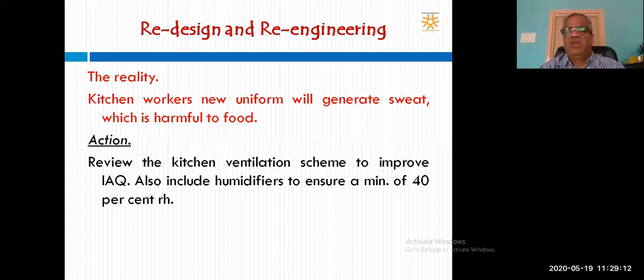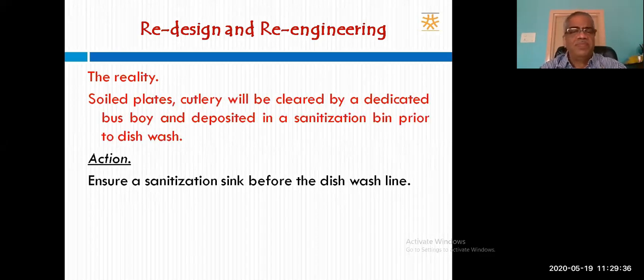We also now need a minimum humidity of 40% in the kitchen. So wherever we have kitchen fresh air systems, whether with evaporative air cooling, controlled humidity, or just outside air sent through filters, we need to incorporate humidifiers to bring humidity levels in the kitchen to a minimum of 40%. This is a big job.